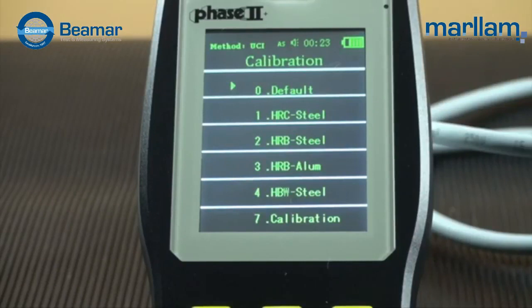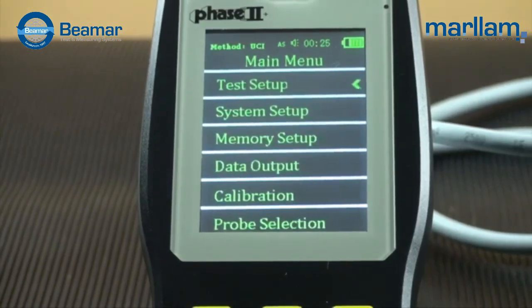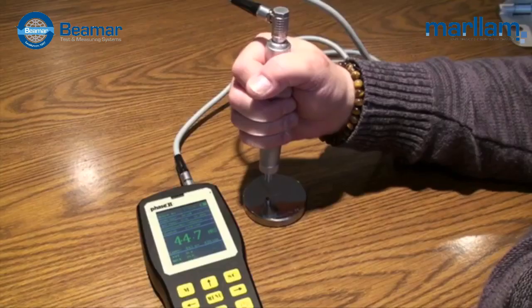Each tester is provided with 4 standard calibrations for different materials: steel to read in HRC, steel to read in Brinell, steel to read in HRB, aluminum to read in HRB. If desired, any other material scale combinations can be added with a known standard for calibration on the fly. They can also be individually named. The menu button on the keypad brings you to a selection of parameter settings: test setup, system setup, memory setup, data output, calibration, and probe selection. We highly recommend that you contact technical support to handle any calibration issues or to add calibrations of new material scale combinations.